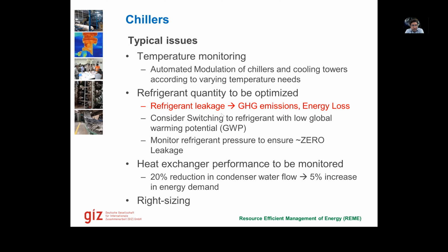I saw recently a factory that was using a brine solution as the main system. This brine solution does not have any global warming potential, which was a good case study for me. And then heat exchangers: when we're using heat exchangers for the chilled water, we also have to look at the condensing that is taking place in the heat exchanger. If the condenser water flow reduces, that means the heat exchanger has started clogging, and a 20% reduction in condenser water flow would mean a 5% increase in energy demand. So this is an important parameter to look at in these chillers as well.